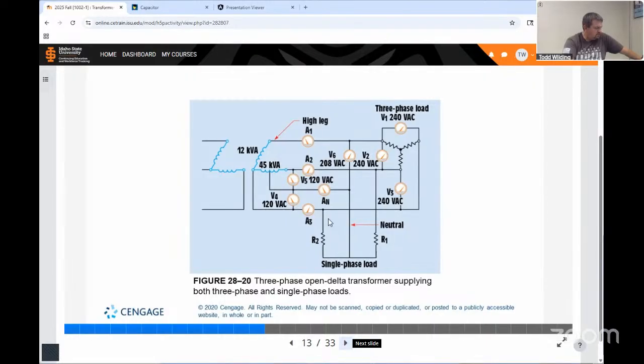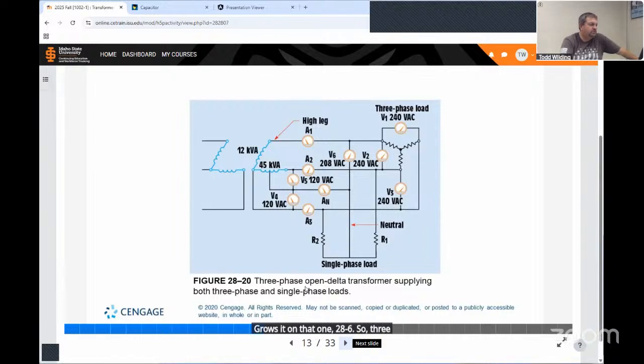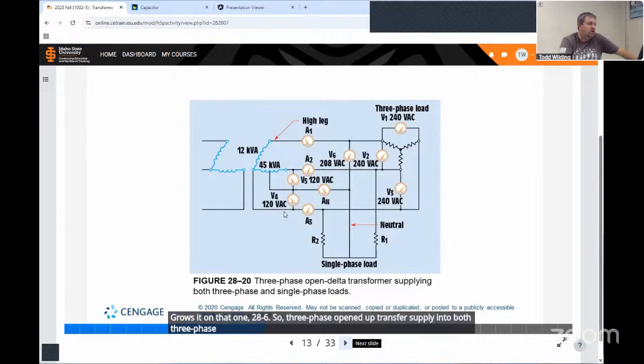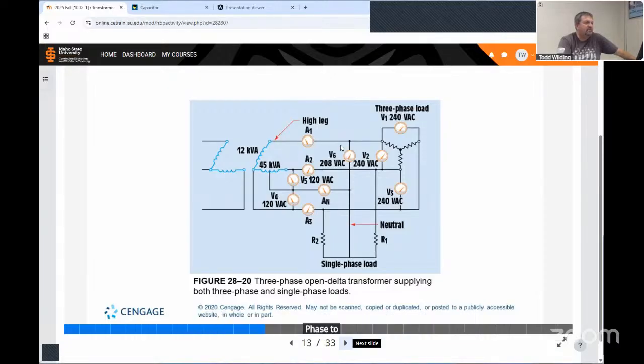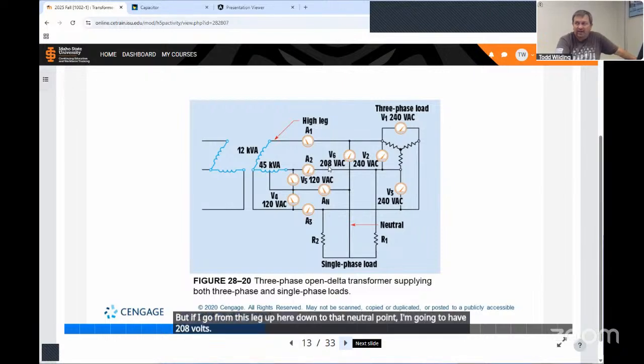Shows it on that one, 28-6. So a 3-phase open delta transformer supplying both 3-phase and single phase. Phase to phase, I'm going to have 240 volts. When I go this phase right here to this neutral point, I've got 120 volts. When I go this phase to that neutral point, I've got 120 volts. But if I go from this leg up here down to that neutral point, I'm going to have 208 volts. They call it a high leg.